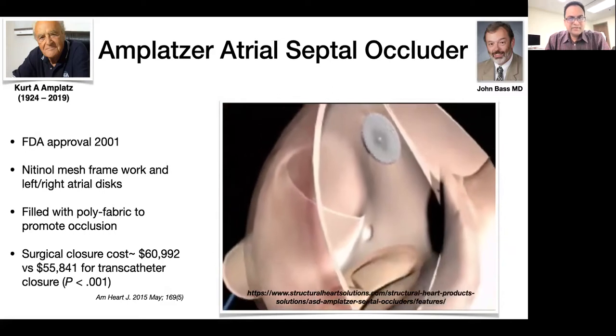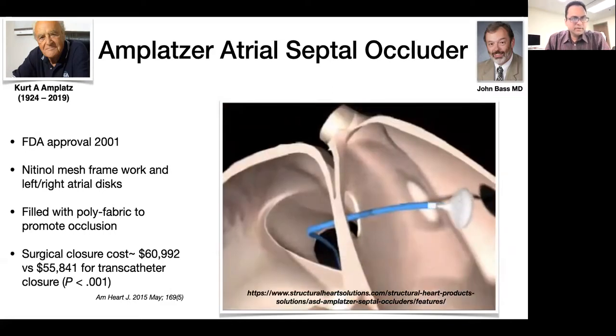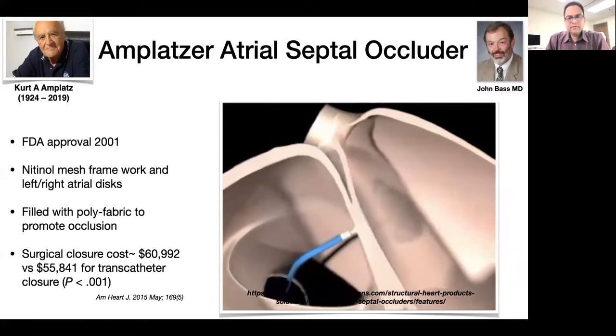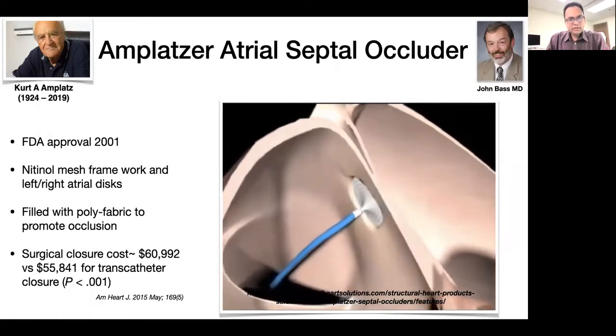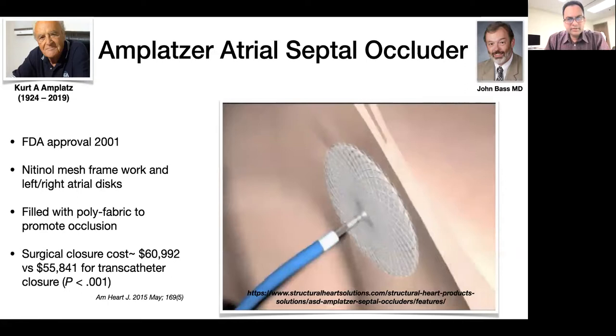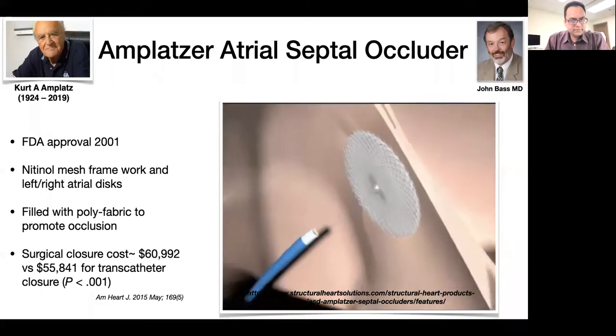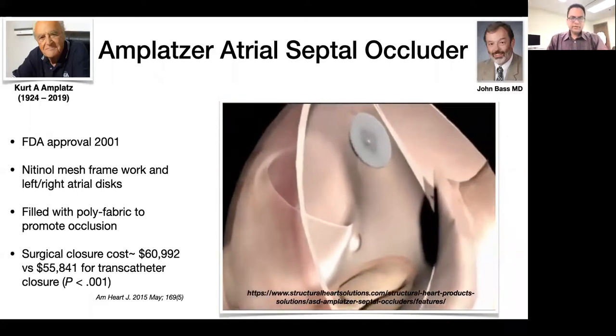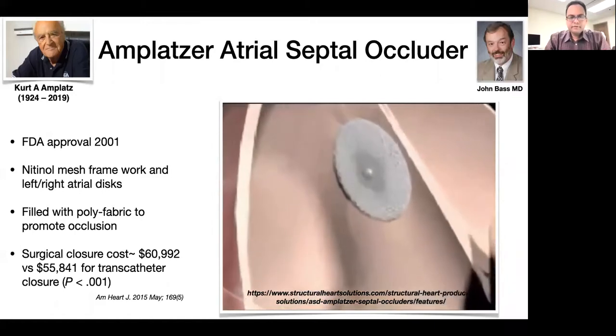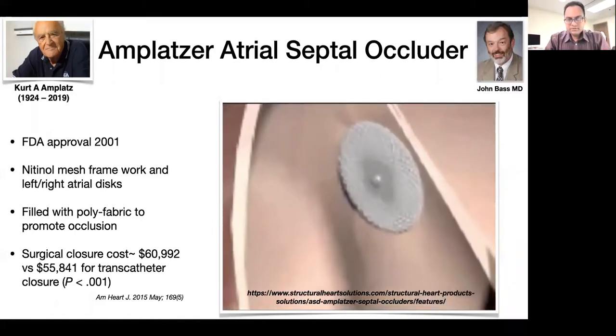And this device has been in the market for more than 20 years. It got FDA approval in 2001. It's made of metal, which is called nitinol. It's a nickel and titanium alloy, and it's used because it has self-memory properties. So irrespective of what shape you pull this device in, it has a tendency to go back to the shape it was designed to. So that way it has a capacity to go through a small catheter. And once it comes out of the catheter at body temperature, it would tend to express the shape that it was formed for. There is some data also suggesting that there is maybe a cost benefit to doing a transcatheter closure versus surgical closure as well.